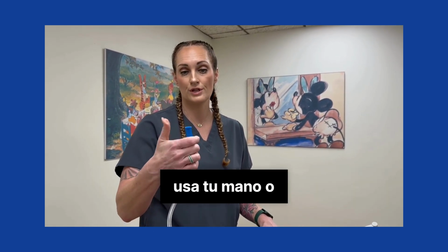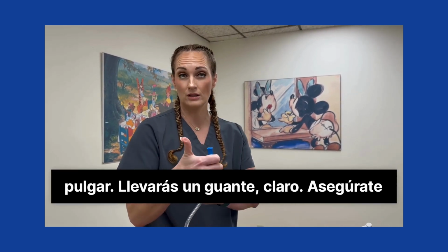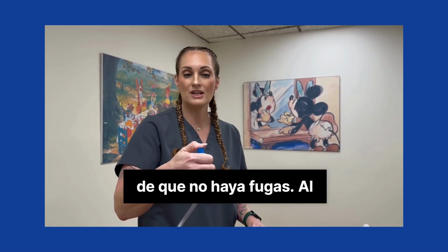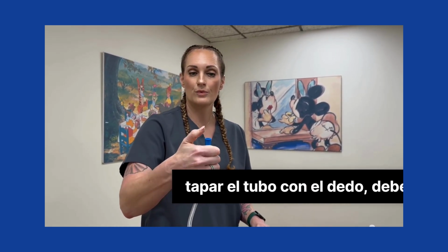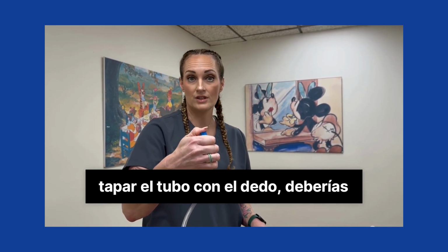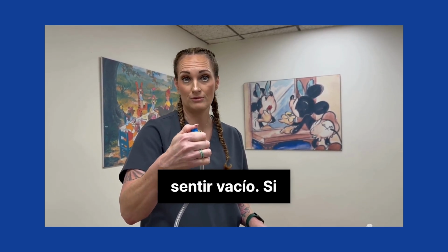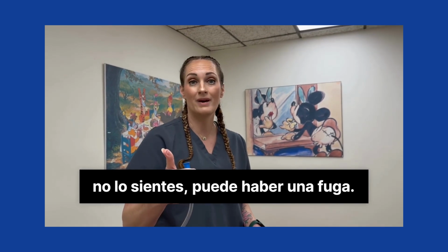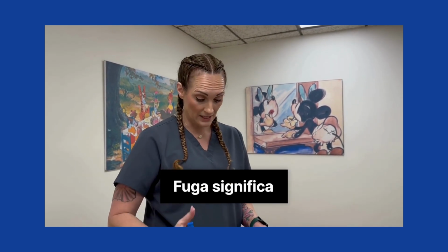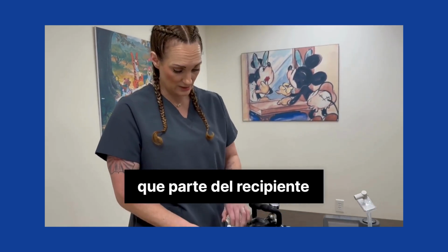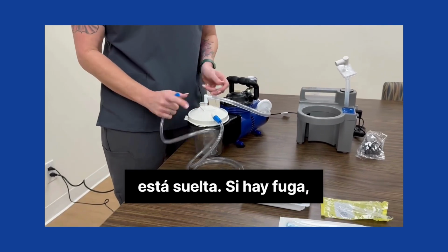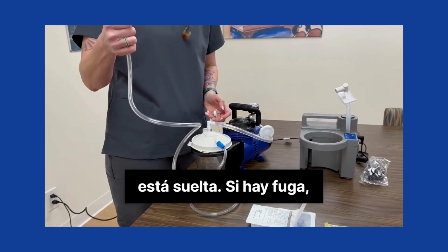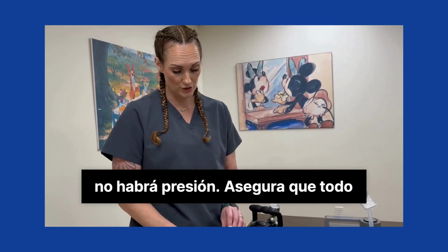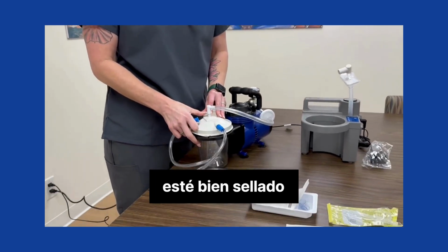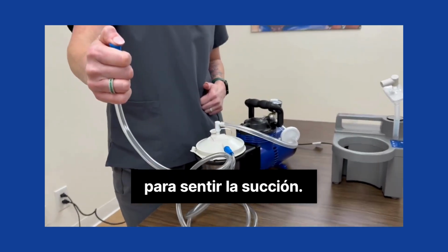Before you connect whatever device you're using to suction the patient, you want to use your hand or your thumb, with a glove on, and make sure there's no leak. When you put your finger over the end of the suction tubing, you should feel a vacuum. If you don't, that means you might have a leak—maybe this part of the canister is off. If you have a leak, you'll have no pressure, so make sure everything is sealed properly so you can feel the suction.